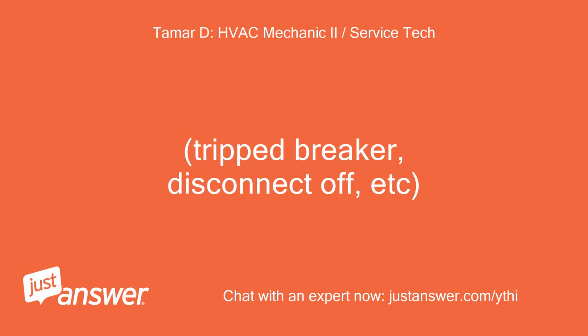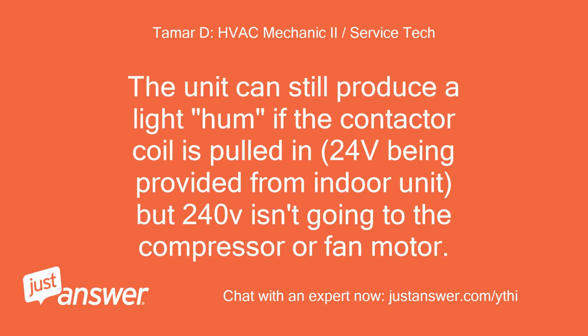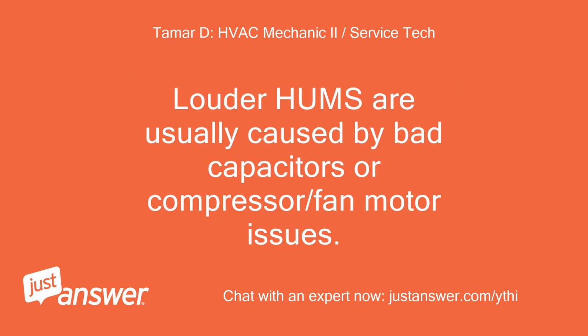Tripped breaker, disconnect off, etc. The unit can still produce a light hum if the contactor coil is pulled in, 24 volts being provided from the indoor unit, but 240 V isn't going to the compressor or fan motor. Louder hums are usually caused by bad capacitors or compressor or fan motor issues.